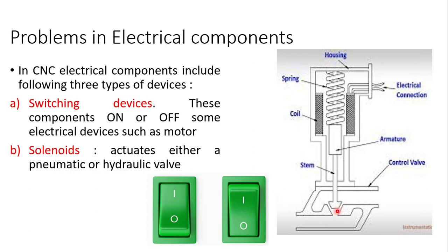This solenoid valve is used in the heaters which you use in the winters. The solenoid valve is there, correct, which is actuating. Then the drive system motor, it is very common. So all the problems related to the electrical component, if it is a motor, like your wiring is not perfect, like the motor burnt out, it's not taking the load. So all these kinds of problems are related to the motor.